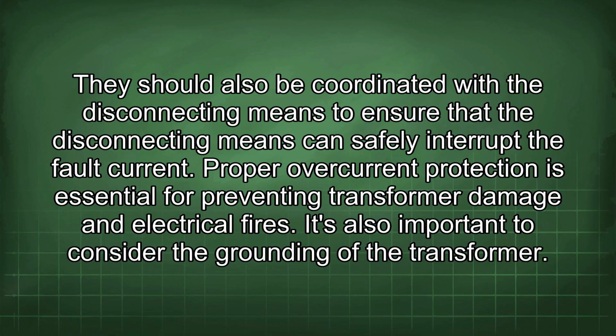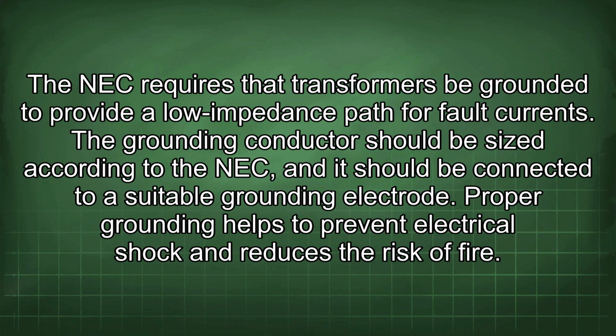It's also important to consider the grounding of the transformer. The NEC requires that transformers be grounded to provide a low impedance path for fault currents. The grounding conductor should be sized according to the NEC, and it should be connected to a suitable grounding electrode. Proper grounding helps to prevent electrical shock and reduces the risk of fire.